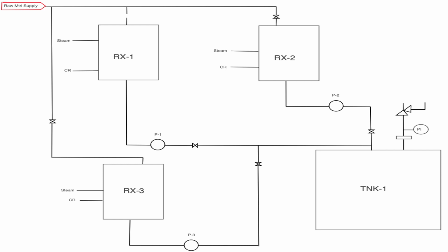So here we have a simplified P&ID or block flow diagram. What I've depicted here on top of what's designated as tank 1 is the design we were talking about earlier, with a relief device and rupture disc combo that has this pressure indication in between. What the pressure indication does is act as a telltale device and lets you know if you're leaking through this rupture disc.